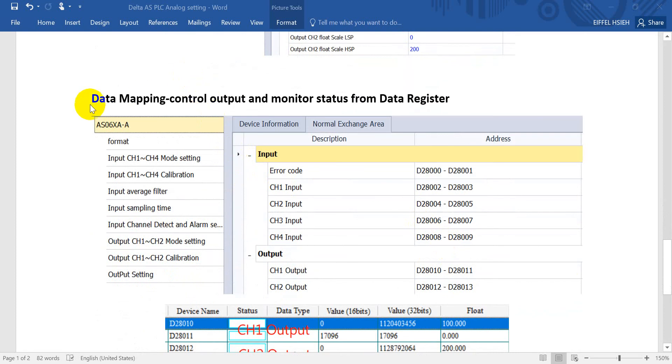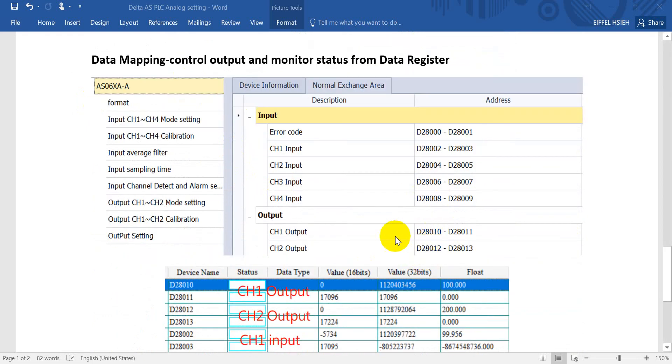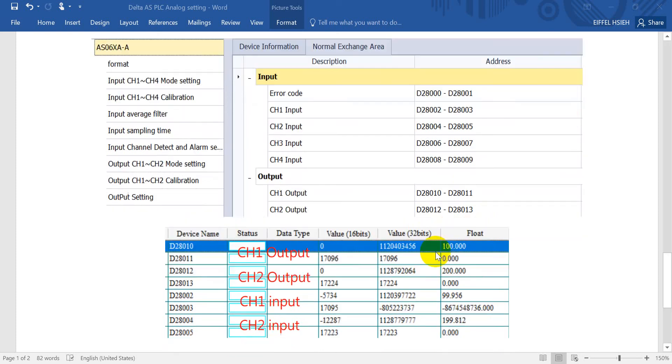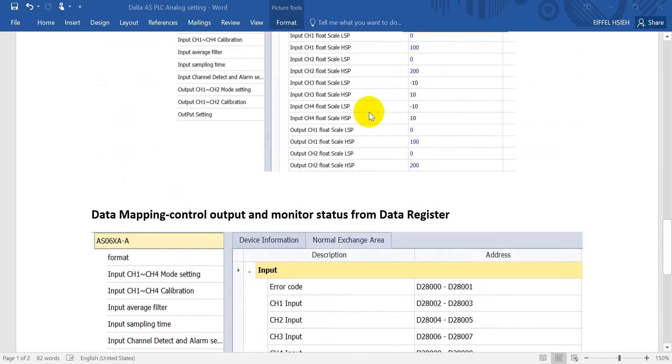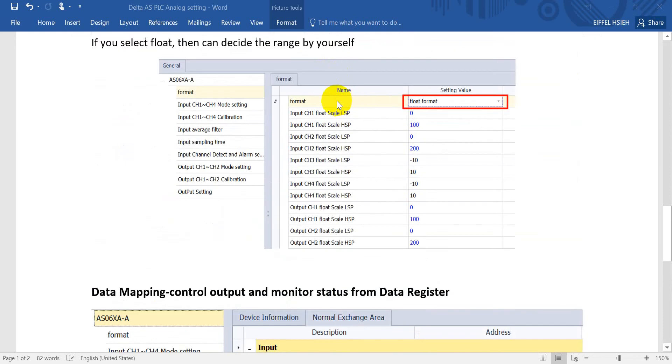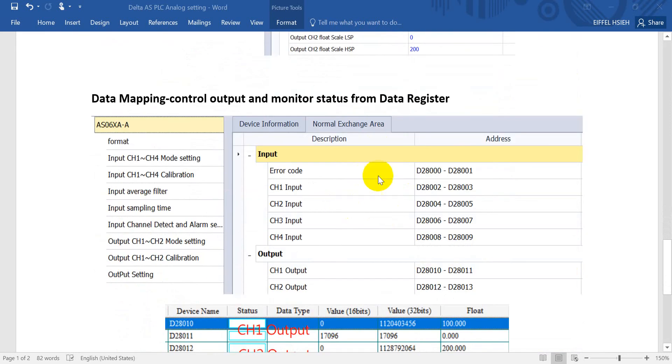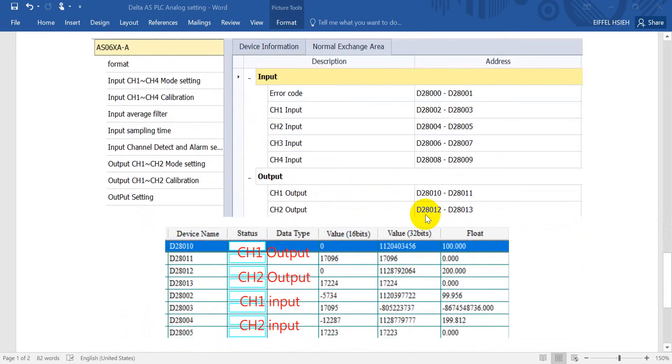You can see the data mapping. That means we can control the output and monitor the status from these data registers. You can find for channel 1 output it will be D28010. It will occupy two words, which means it is a double word. Later we will show both selecting float or integer, so we will show you the difference.